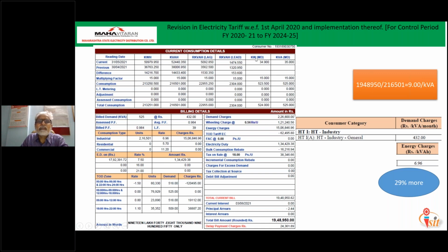Now this is the demand, kW demand, kVA demand. So accordingly, for this particular month, the demand was 525. So 525 multiplied by this 432. So these are the demand charges. Now wheeling charges are there, 0.56 multiplied by this, it will be wheeling charges. Now energy charges, as per the tariff, 6 rupees 96 paisa multiplied by these electric units. So here they have calculated the energy charges.